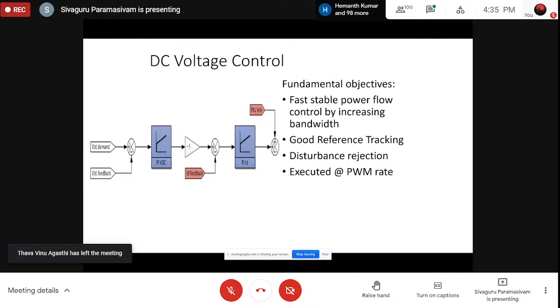So the voltage control block is nothing but, there is a VDC demand. VDC is the voltage of the DC. The VDC demand is set inside the inverter. You can refer this to the MPPT as well. So we can define here, I need a 600 volt demand, but when the actual voltage is coming like 500, 580, whatever it is, then we use a PID controller, a proportional, integral and derivative controller, to get the system's feedback and correct it with our algorithms.